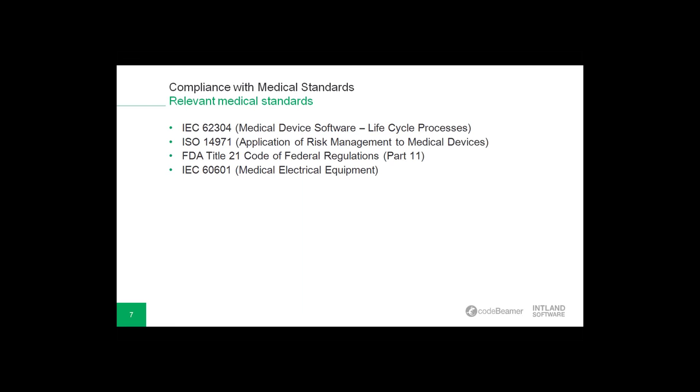And the last one in this section is the IEC 60601. It is actually a collection of standards rather than one standard, all of which aim to govern the safety and effectiveness of medical electrical equipment. The first part of the standard is titled General Requirements for Basic Safety and Essential Performance. It's the section that gives general guidance on the requirements of the standard, and it also contains a section, 14, on the safety used in medical devices.